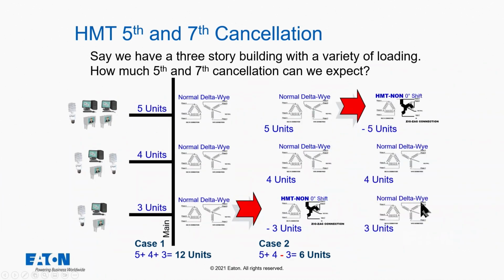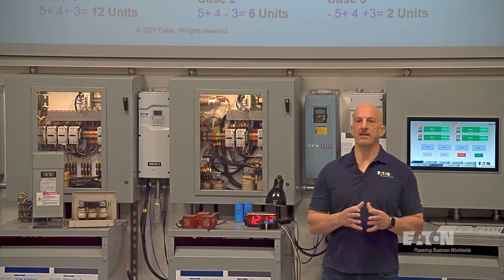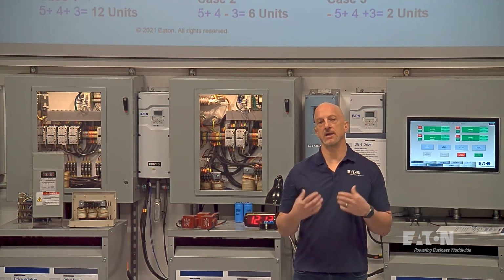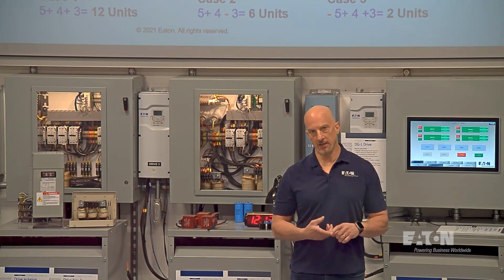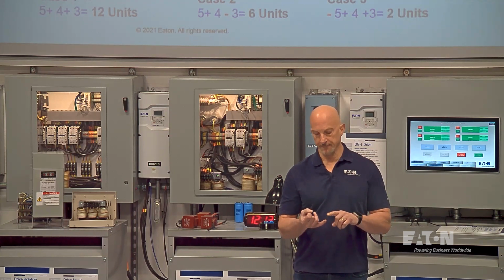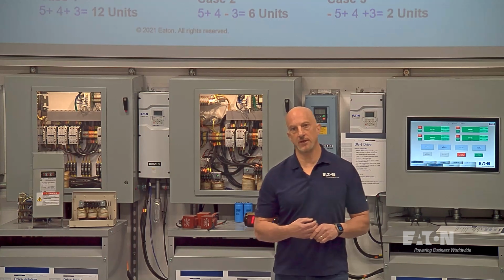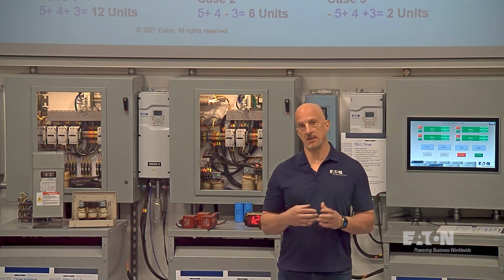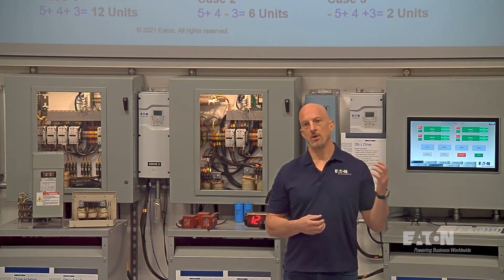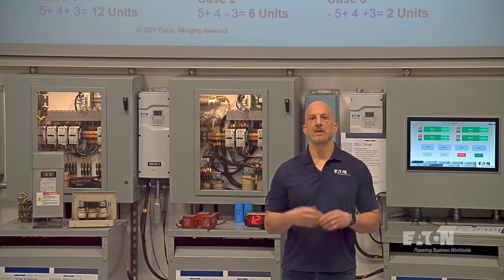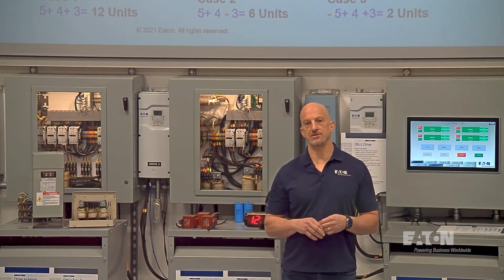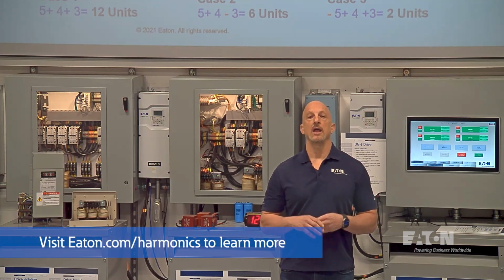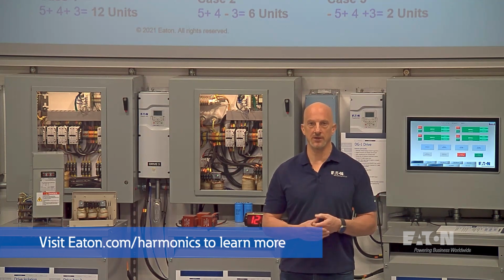And then if I strategically pick the right one, minus 5 plus 4 plus 3, I could go down to 2. So picking the right phase shifting transformer and actually combining those transformers to do harmonic mitigation by cancellation is the way that you get harmonic mitigating transformers to work for you to eliminate harmonics. So again, third harmonics don't come through the primary of the transformer. They circulate and go back to the load from the zigzag winding, or in a delta-Y, they go from the delta winding to the load. The fifth and seventh, with strategic combinations, you can cancel the fifth and seventh from 2 different systems. And again, you could do 18-pulse or 24-pulse or even higher if you wanted to cancel harmonics.